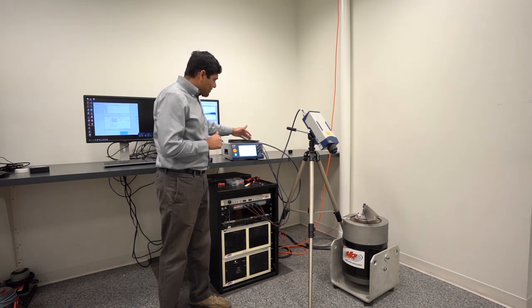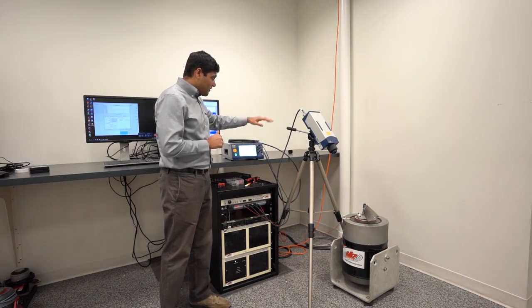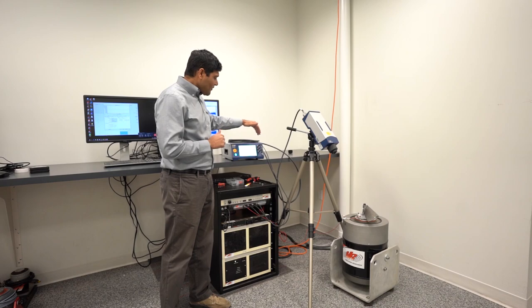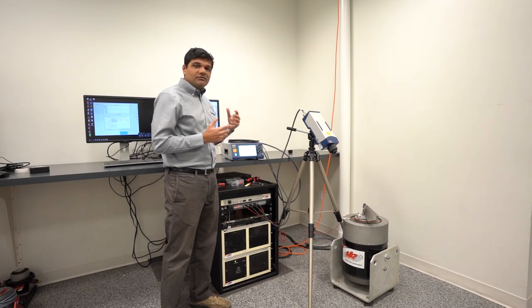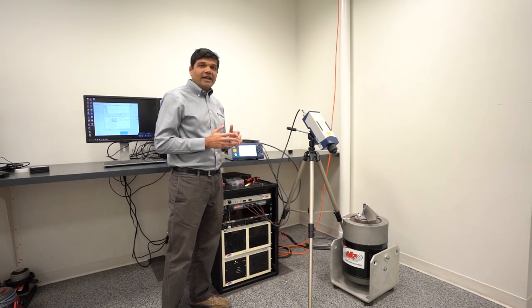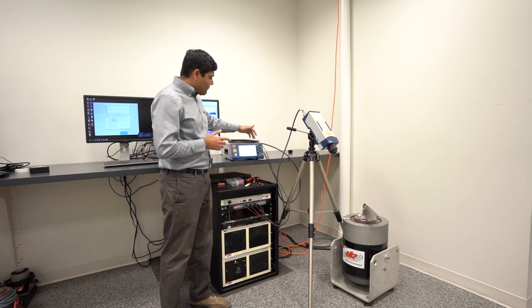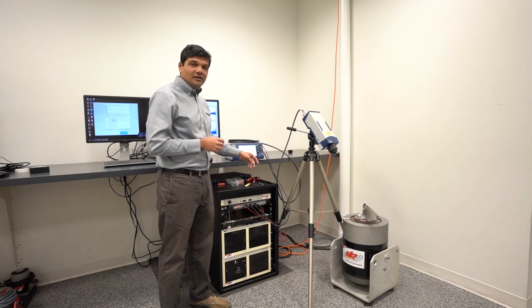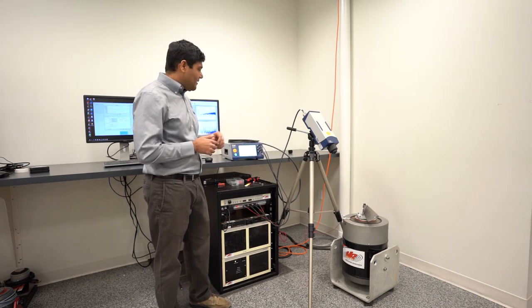So here you can see we have three different outputs on this particular system. A vibrometer fundamentally measures both velocity and displacement. In this case, we have velocity, displacement, and differentiated acceleration as well, derived from velocity.